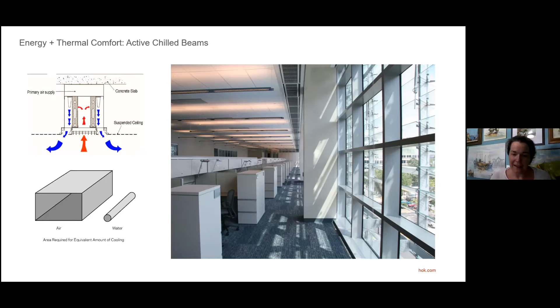We do have daylight harvesting controls, but for photography everyone likes to override those and let everything light up so you can see it all on. We also had 100% energy recovery ventilation, using enthalpy wheels for general exhaust and glycol runaround loops for the lab exhaust. And we had an energy recovery chiller, or heat shift chiller, which basically harvested waste heat from lab equipment or other equipment and replugged it into outside air or other systems as needed—just moving heat around the building rather than exhausting it and generating new heat when heat was needed, using it for reheat after latent cooling processes took place.